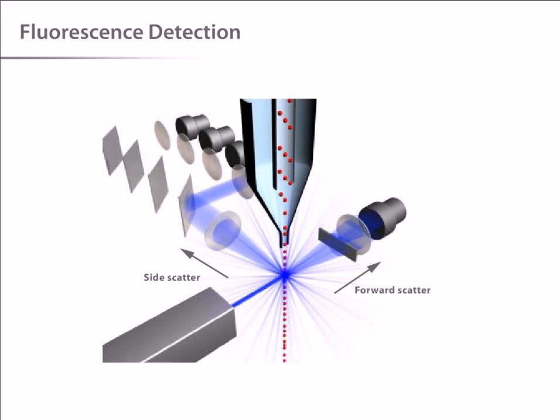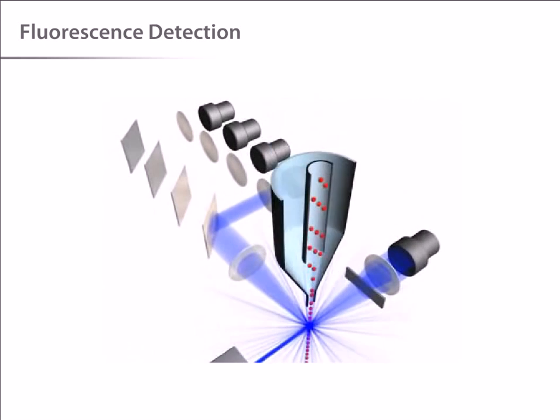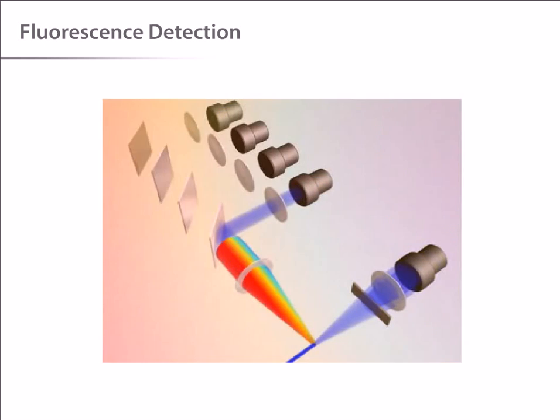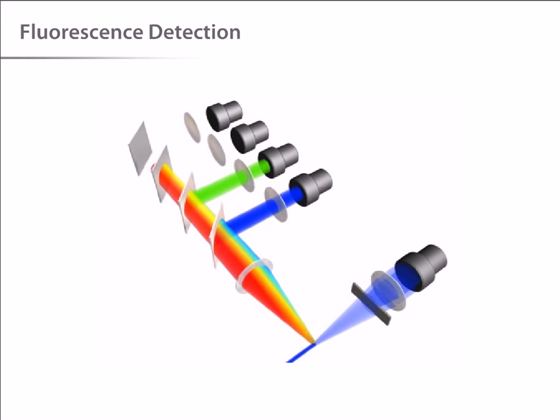How is this fluorescence information collected? The fluorescent light, coming from labeled cells as they pass through the laser, travels along the same path as the side scatter signal. As the light travels along this path, it is directed through a series of filters and mirrors so that particular wavelength ranges are delivered to the appropriate detectors.